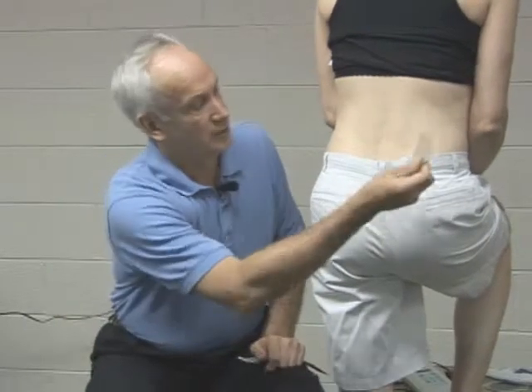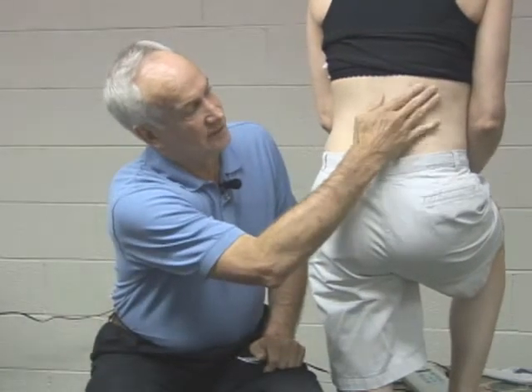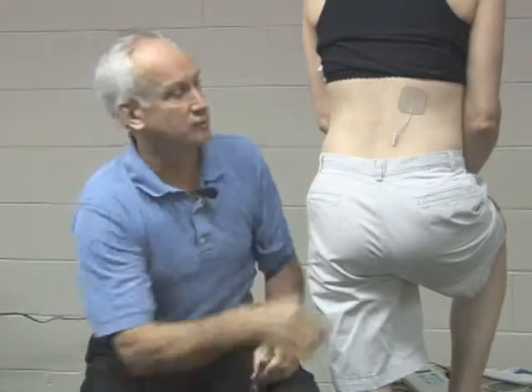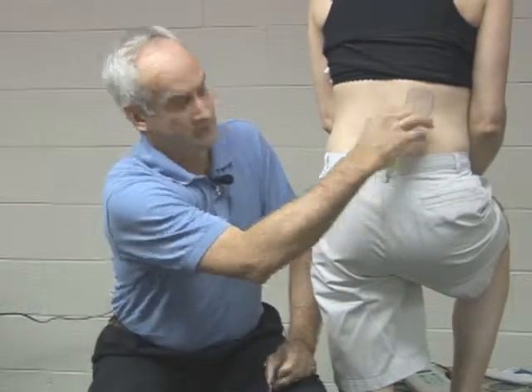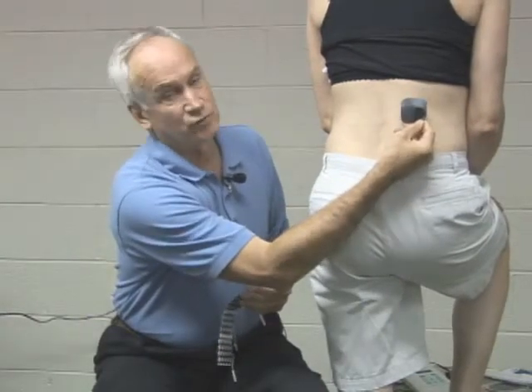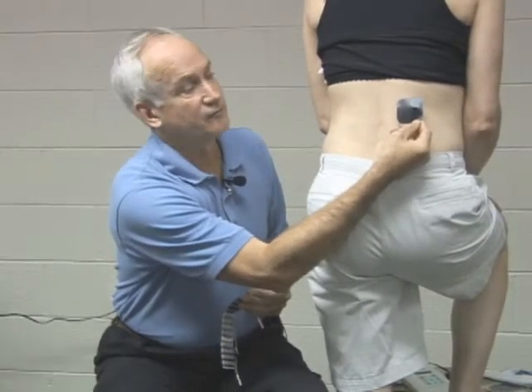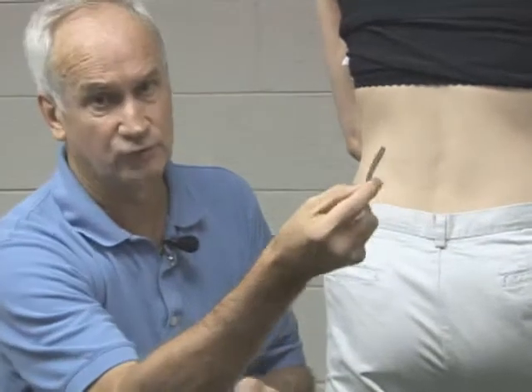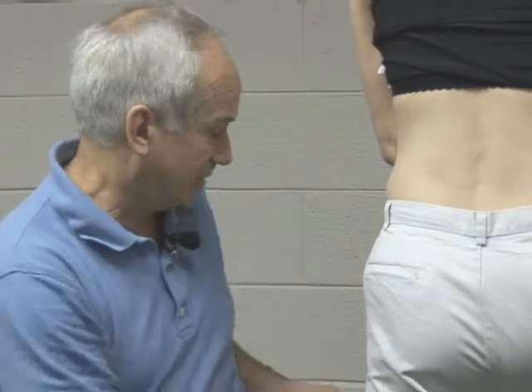Here's a type of electrode you really don't want to use for chronic low back pain. This electrode is one and three quarters by one and three quarters — it's a pretty small area. If you look at this electrode, that's where all the electricity has to come out of. Especially on interferential mode, that's not a large area. So your traditional two-by-two electrode for interferential mode is really not acceptable, especially for low back pain.